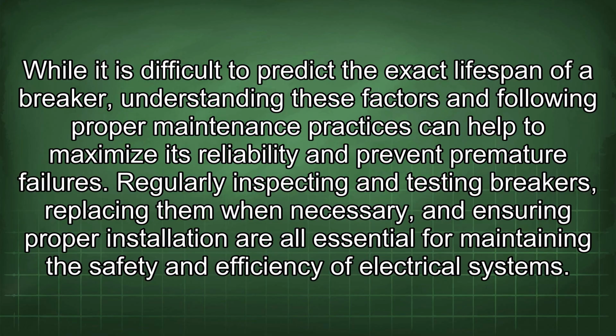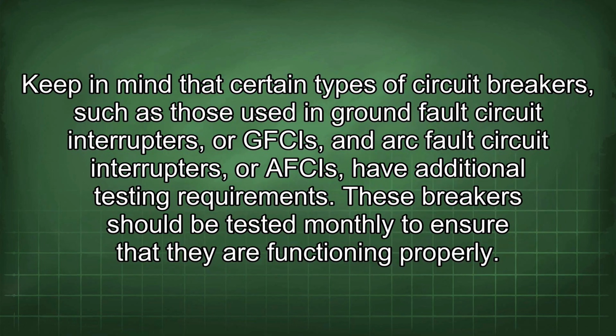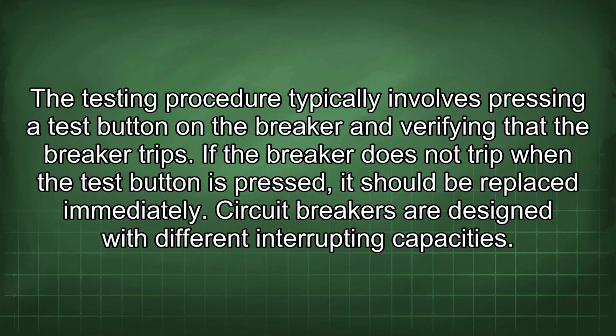Regularly inspecting and testing breakers, replacing them when necessary, and ensuring proper installation are all essential for maintaining the safety and efficiency of electrical systems. Keep in mind that certain types of circuit breakers, such as those used in ground fault circuit interrupters, or GFCIs, and arc fault circuit interrupters, or AFCIs, have additional testing requirements. These breakers should be tested monthly to ensure that they are functioning properly. The testing procedure typically involves pressing a test button on the breaker and verifying that the breaker trips. If the breaker does not trip when the test button is pressed, it should be replaced immediately.